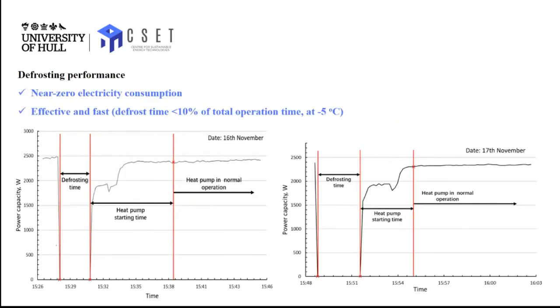Look at defrosting. For our technology, we make use of ventilation to defrost the heat pump. Our defrost time is reduced to very short, only 10% of the total operation time at minus 5 degrees Celsius, whereas a traditional heat pump has a much longer defrost time, 20% of operational time. That's why it uses significant electric energy for defrosting, which is a complete energy loss.